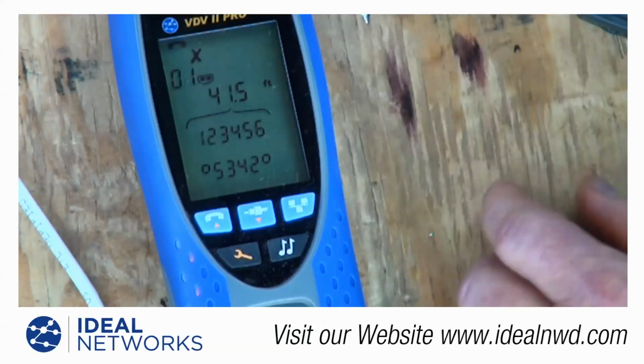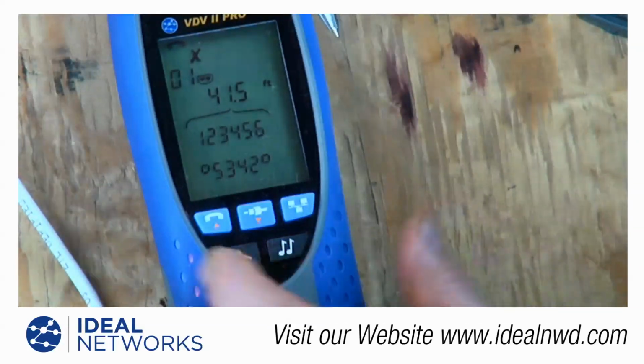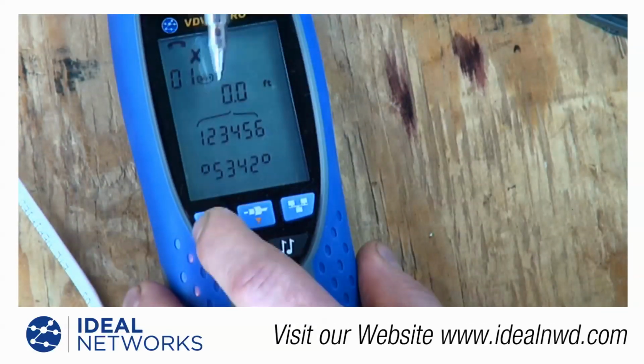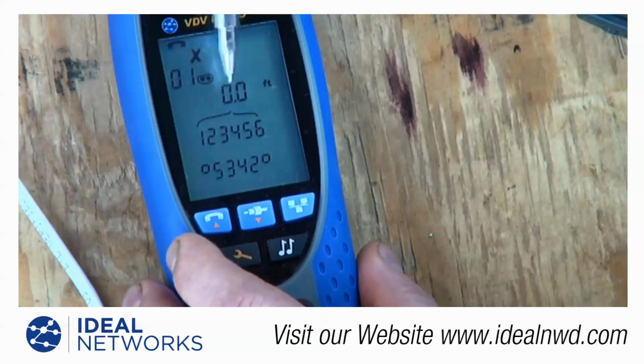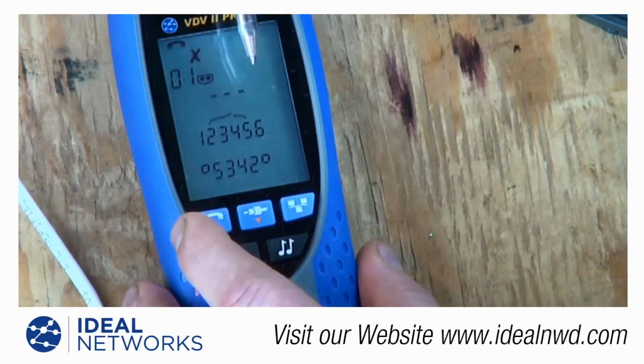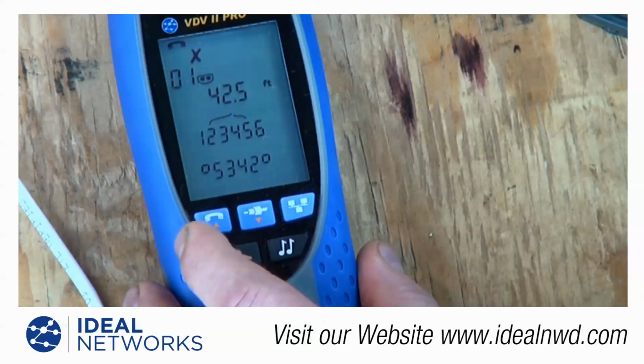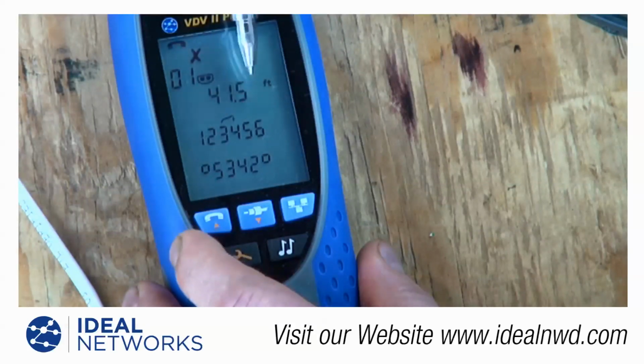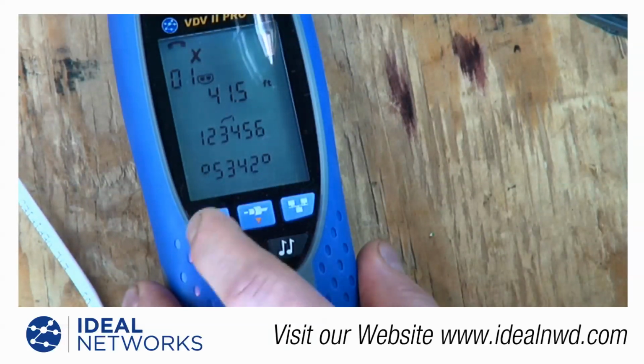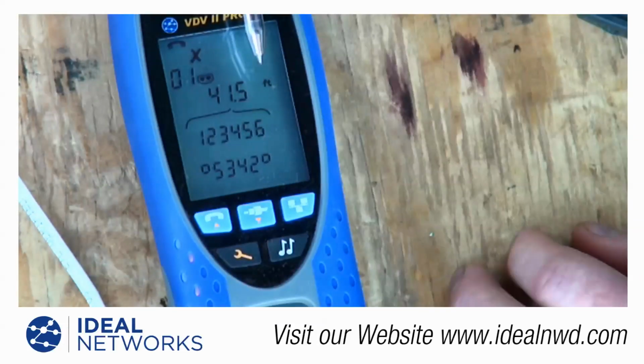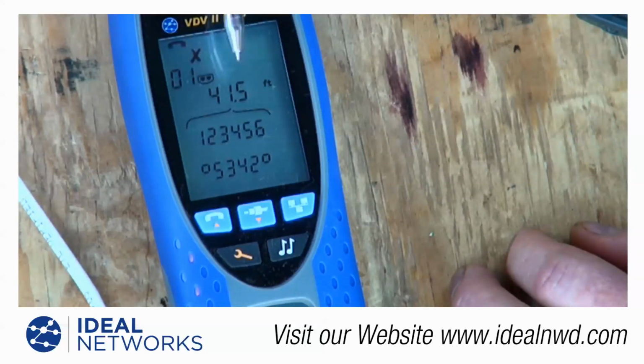Now, I could, if I wanted to, by looking at length again, by pushing the phone button, it's going to look at the length of pins 1 and 2, which is 0 feet because there's an open in it. 2, 5 is indicating about 42.5 feet, and 3 and 4 is indicating about 41.5 feet. So, again, the tester can be used to identify a live analog signal, and it can also be used to test cabling for any miswires that are out there. So it's very helpful, again, when troubleshooting and working with phone circuits.